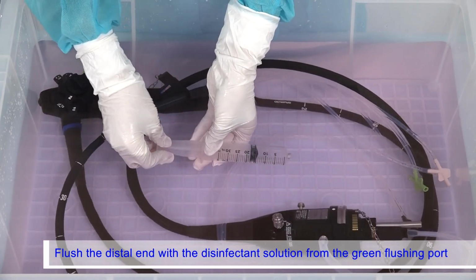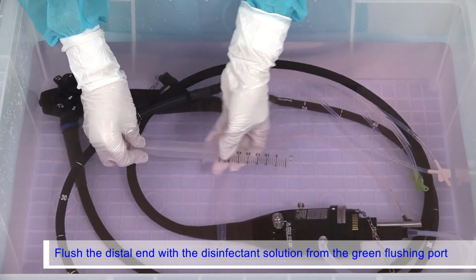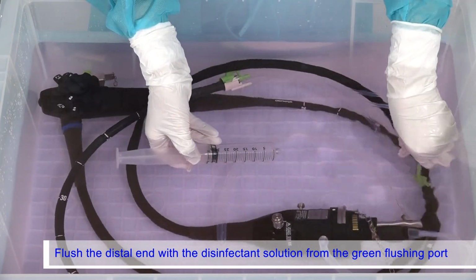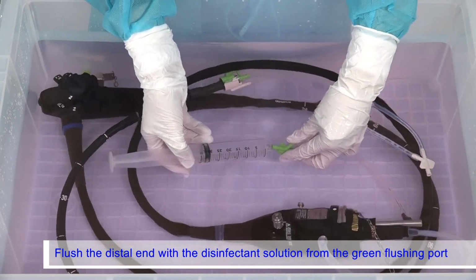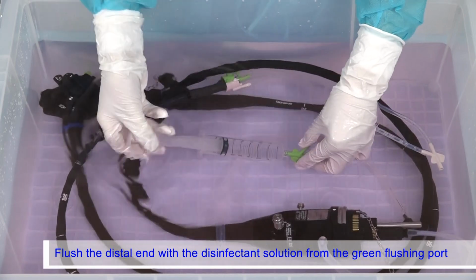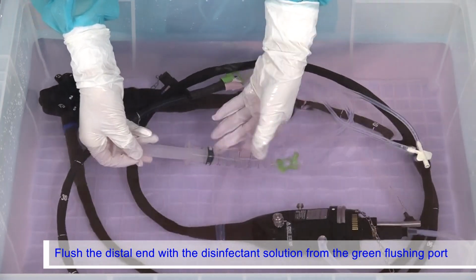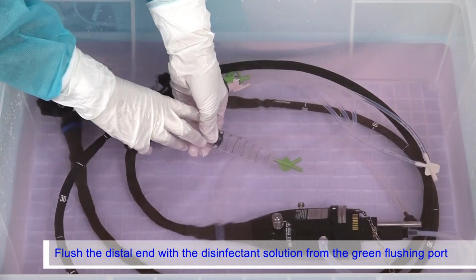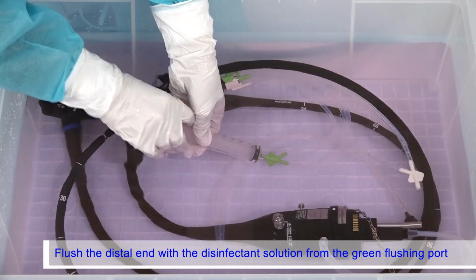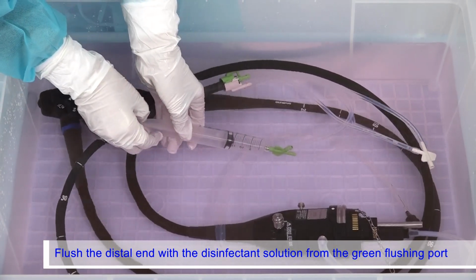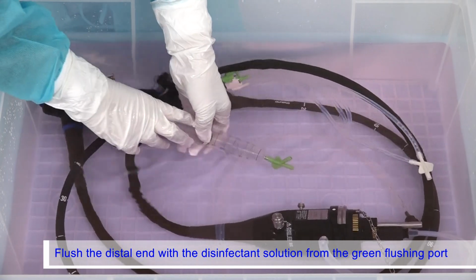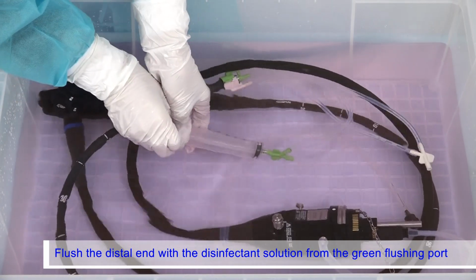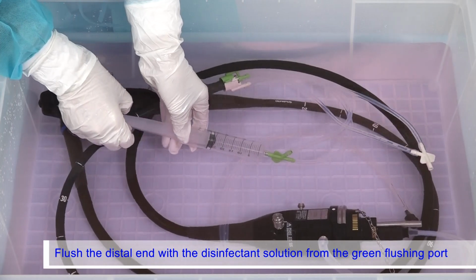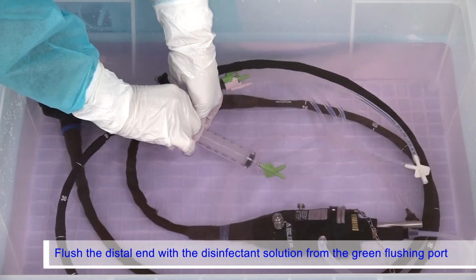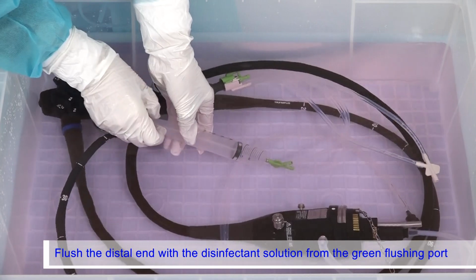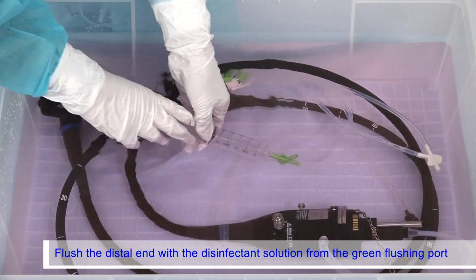While immersing the syringe completely in the disinfectant solution, slowly fill the syringe with the disinfectant solution. Attach it to the green flushing port of the distal end flushing adapter and forcefully flush the distal end with 30 milliliters of the disinfectant solution. Then slowly pull the syringe plunger to fill the syringe with the disinfectant solution and forcefully push in the plunger to flush the distal end with additional 150 milliliters of the disinfectant solution.